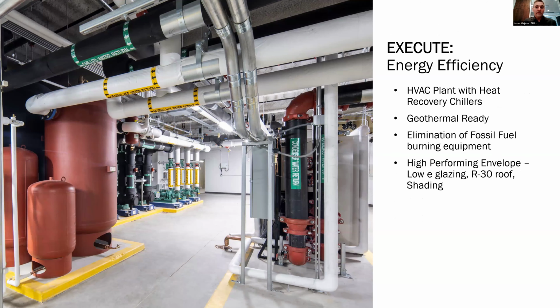So the plant for the new wing is a satellite plant that I mentioned. It uses a tempered water loop from the main central utility plant. And how we gain energy efficiency is through the use of heat recovery chillers. These chillers are geothermal ready, and this new wing could operate completely independently from the central plant if that geothermal loop was in place. It can also operate independently in its heat recovery mode. So this is part of the decarbonization strategy that really aligns with that mission of sustainability for the museum.